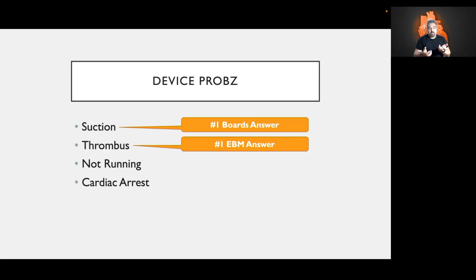Now, a suction or a suck down event, again, this is an early complication that tends to occur immediately after implantation, usually while the patient is still in the ICU. This is because there is not sufficient preload for the pump speed. And in a recently implanted VAD, this can be because the pump speed is set too high. But later on, it can be because the patient doesn't have enough preload. They got over-diuresed or something, or they're bleeding or otherwise volume down. Now, what happens here is the pump speed is too high, so that inflow cannula gets sucked towards the septum, the ventricular septum usually, and it kind of gives it a hickey. And the controller understands that there's no flow now at this point, so it stops the pump temporarily so it'll come off and then restarts it. So there'll be alarms going off. If you were to be auscultating, you'd actually be able to hear the pump stop spinning and then resume spinning.